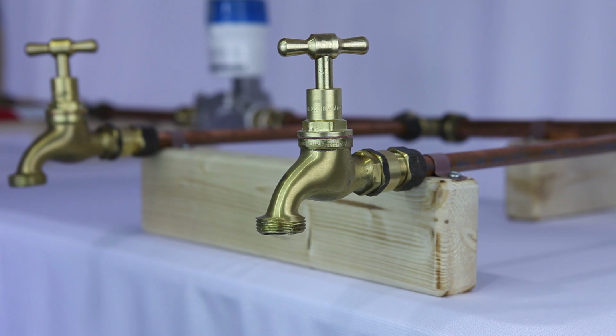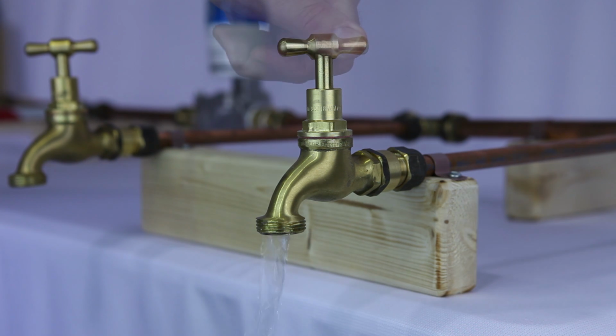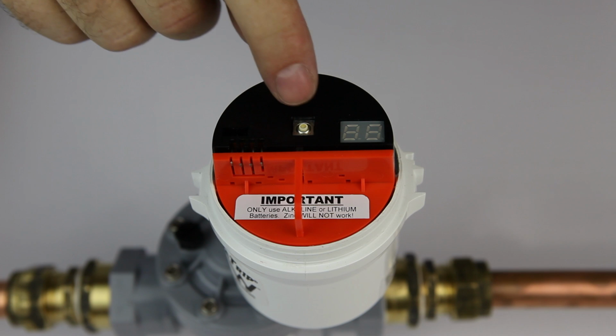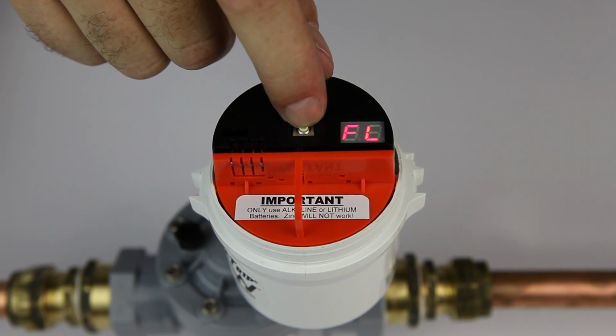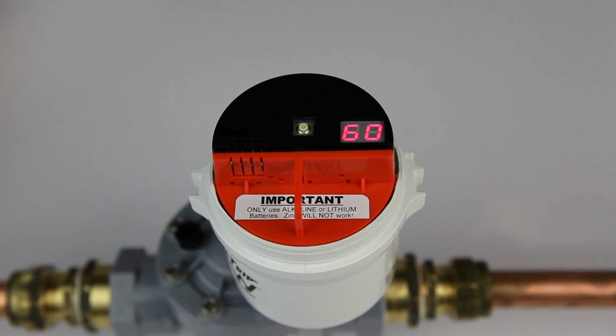The flow sensor functionality test. If the flow sensor continues to detect water flow and you are sure there is no water flowing anywhere, you need to check the flow sensor is working correctly. To do this, turn on a tap. Hold down the button until you see FL and let the countdown start.